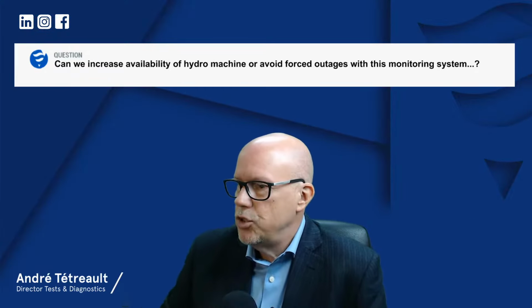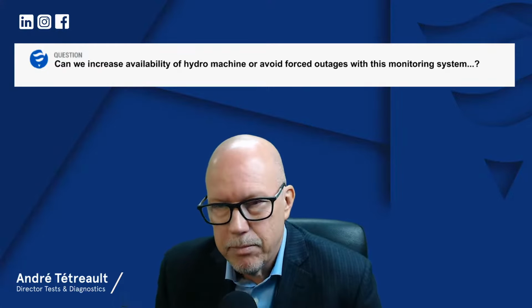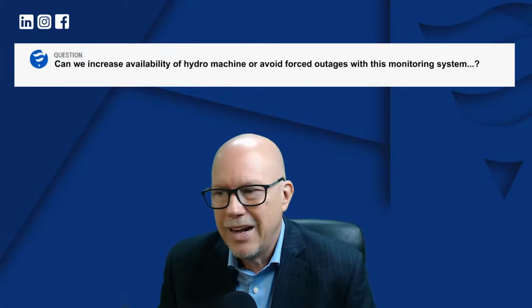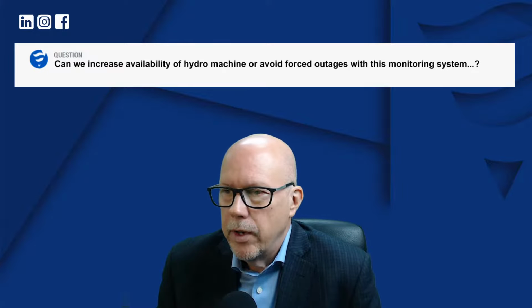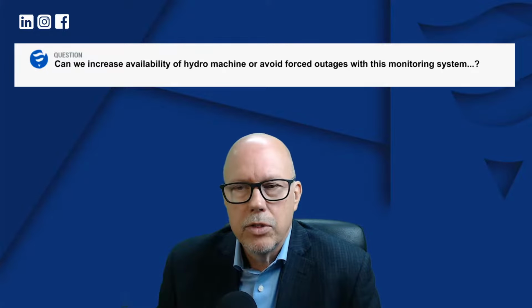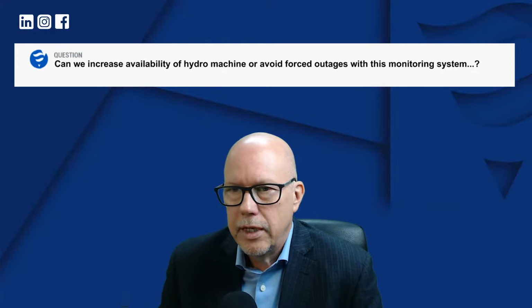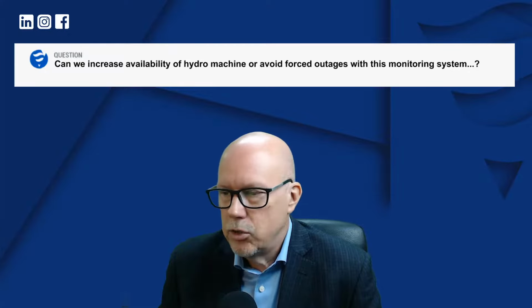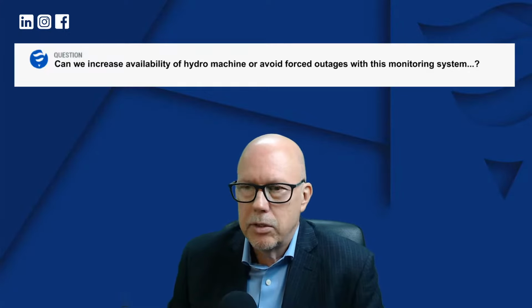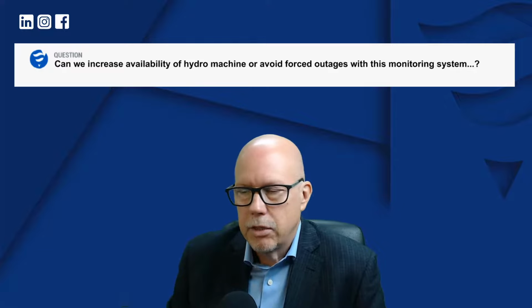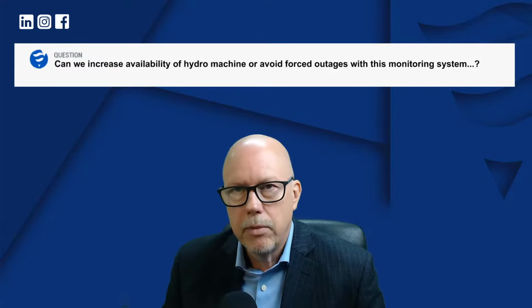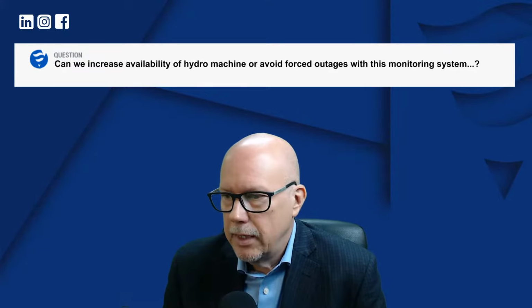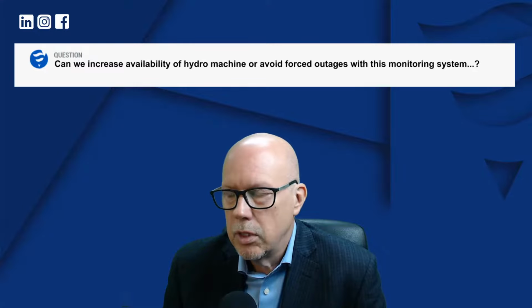Let's say you have an issue with rotor pole temperature, or you have an issue with a guide bearing. You are able to put those actions that you need to undertake in your plan, so that you can have the personnel, you can have the parts, you can have the allocation of space, and get all the permits so that you can go in there and fix the issues.